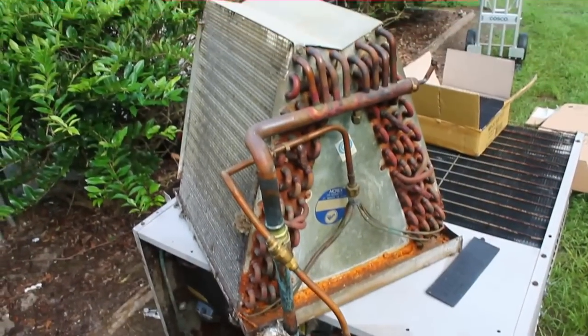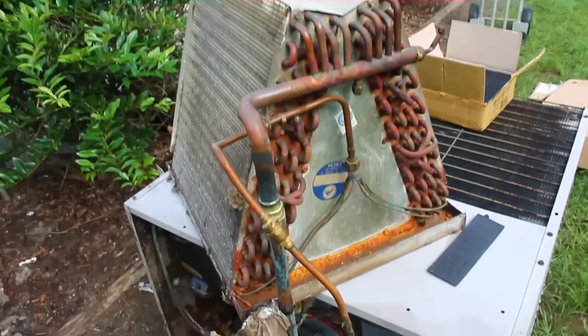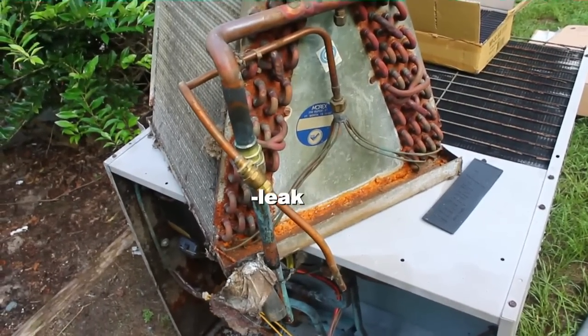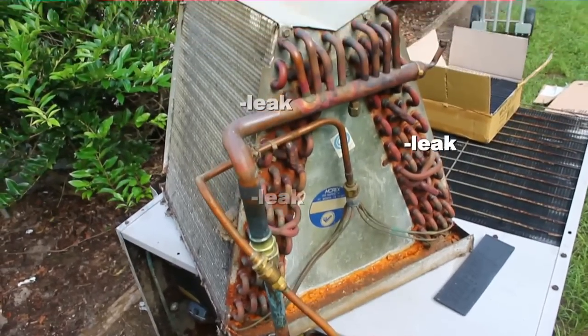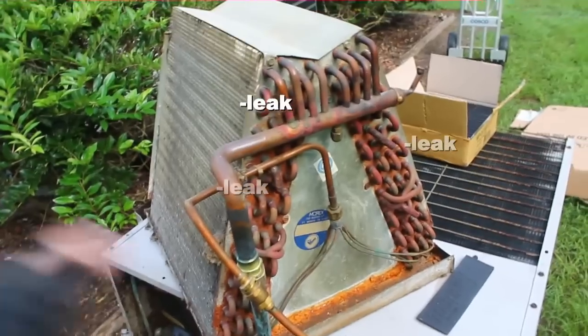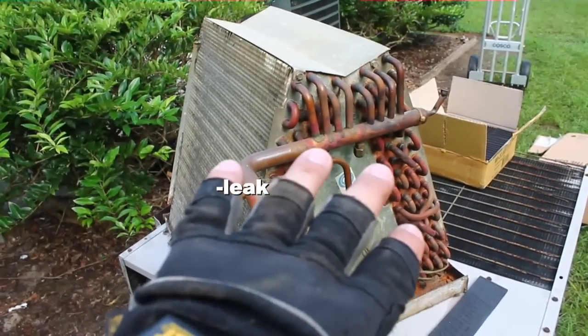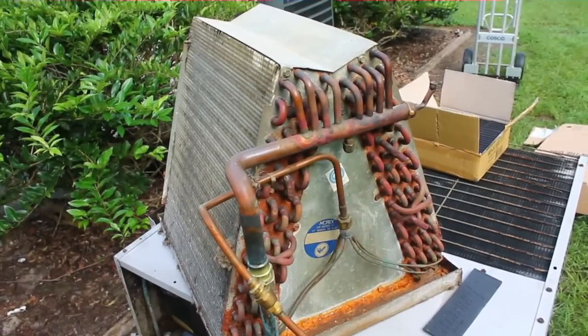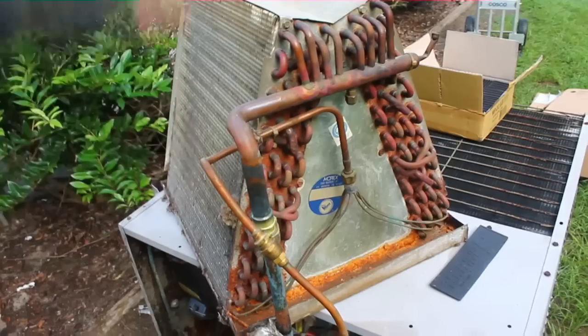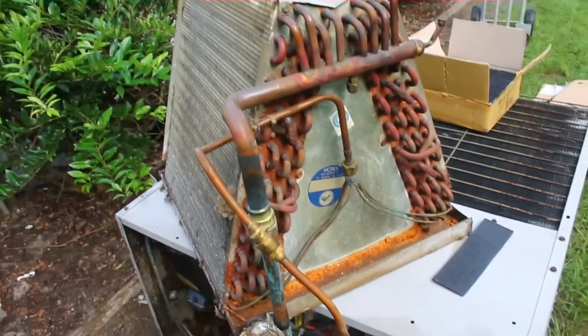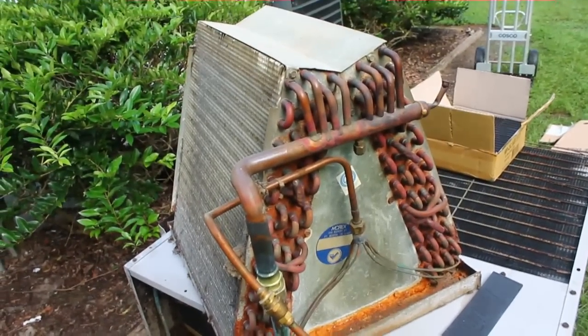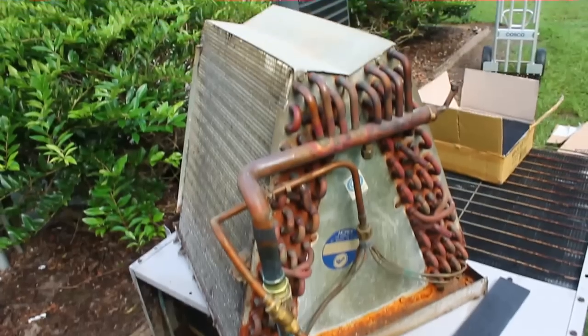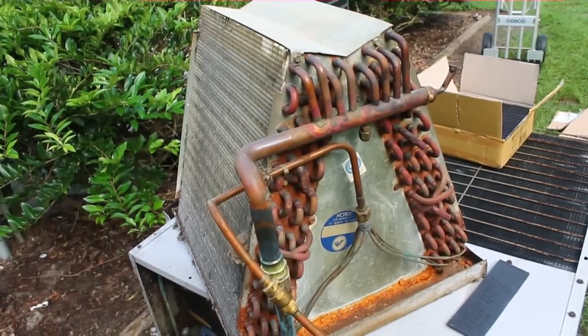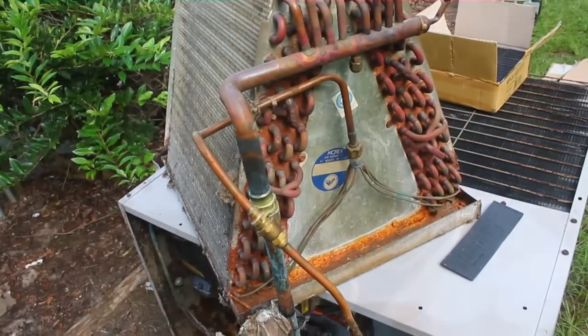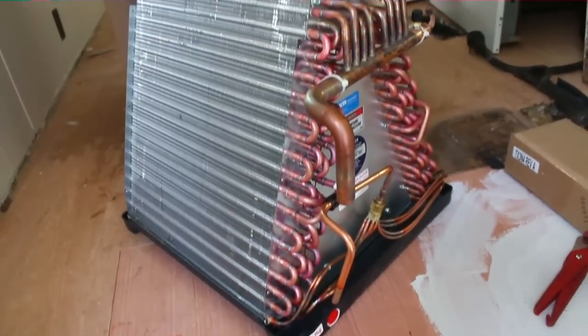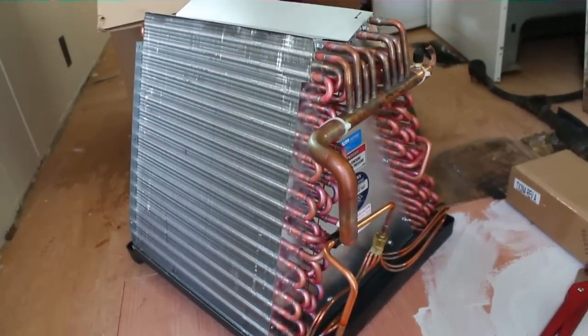This is our indoor coil. Came off the top of the electric furnace. Old Mortex coil. Was leaking in about 100 spots. I remember running a leak detector across this thing a couple years ago, the Yellow Jacket leak detector, and just everywhere, beep, beep, beep, everywhere. Definitely a leaker. She's a couple years late getting removed, but that's how it is with rental properties. This is our new, much healthier looking Mortex coil.